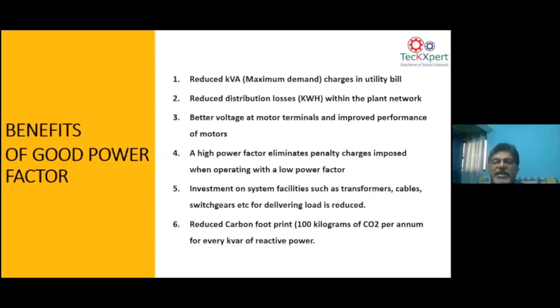Now if you put a capacitor near the motor, the capacitor will exchange energy from its electric field to the motor's magnetic field and improve the power factor at the motor end. Thereby you can reduce the losses from the transformer to the line. Similarly, at the motor terminal it can improve the voltage, and it can improve the performance of the motor also. Low power factor means you will get penalized, so a high power factor eliminates the penalty charges, as we all know. It also reduces the investments required on the whole power system. You can reduce your transformer sizing and your cable sizing by improving your power factor.